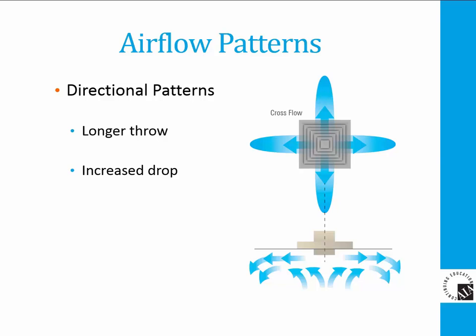However, because there is less induction, there remains more cool air in the jet as it slows down, and at velocities less than 75 feet per minute, buoyancy will separate the jet from the surface of the ceiling, causing the possibility for drafts to occur in the occupied zone below that area.